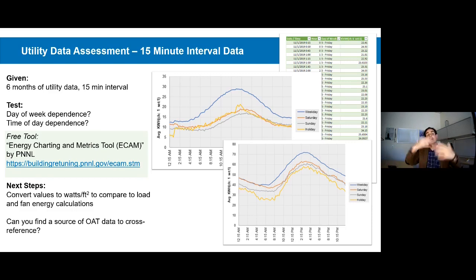And so you can immediately start to get some charts like this, and those values can connect to our design assumptions. For myself, I always like to take these numbers and divide by square footage because our load calculation assumptions are usually in watts per square foot, right? Like lighting and plug loads, etc. We talk about those in per square foot.